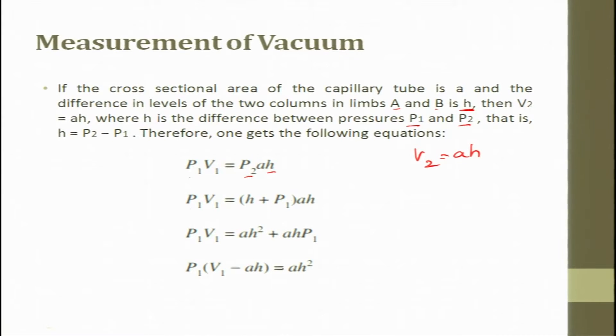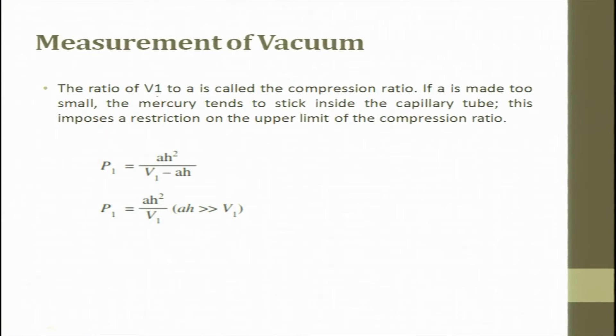Re-altering the equations, P1V1 = (H + P1) × AH, which gives AH² + AH·P1. Moving P1 to one side: P1(V1 − AH) = AH². The ratio of V1 to A is called the compression ratio. If A is made too small, the mercury tends to stick inside the capillary tube, which imposes a restriction on the upper limit of the compression ratio.